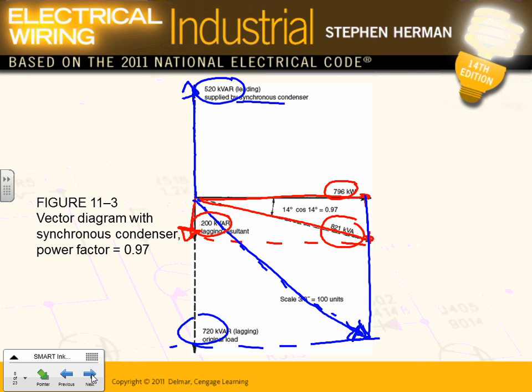But when you add the capacitive kVAR, this is my capacitive, and this is my inductive. These will push against each other, guys, in the opposite direction, so they subtract from each other. By doing this, look what happened. I reduced my kVAR and my kVA to 821. My power factor increased to 97%. Excel is happy. I am not penalized. I'm not paying more money. So everybody's happy, right?